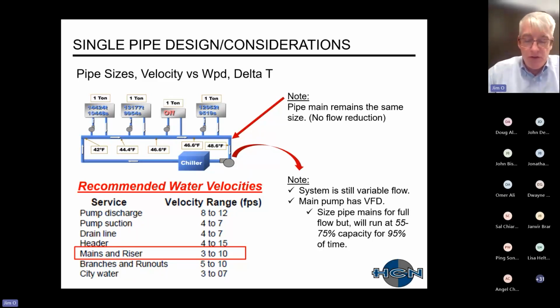Typically what is done, similar to before, is that the pipe size is sized for the full flow, but traditionally, depending on your system and diversification, etc., your flow will run at 50 to 75% of the full capacity for 75 to 95% of the time, etc.